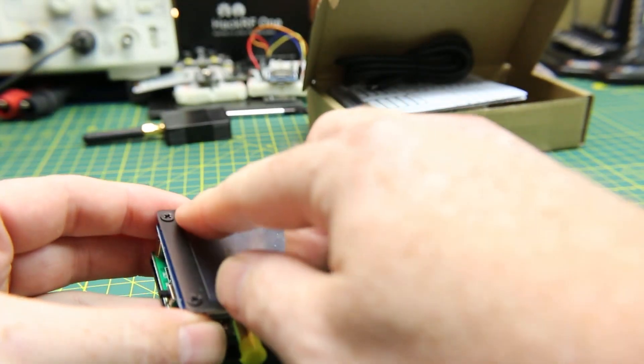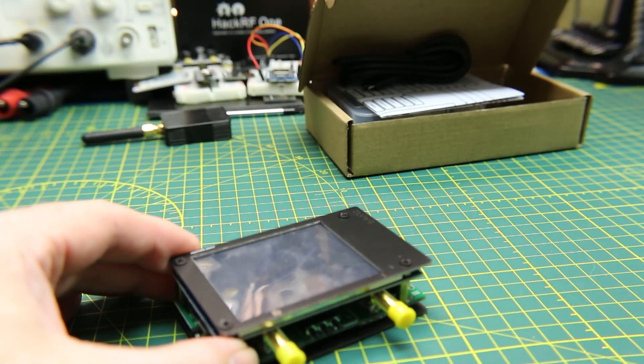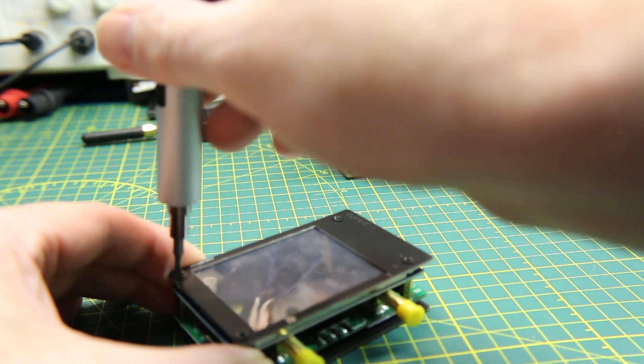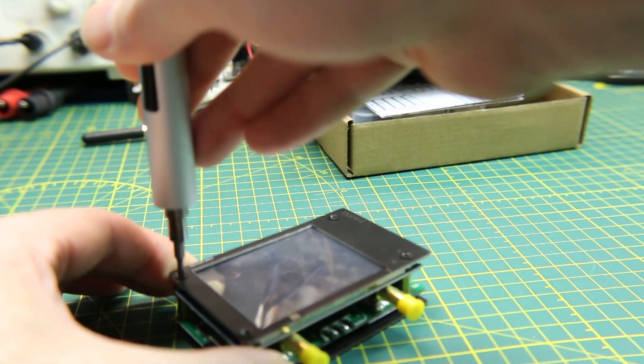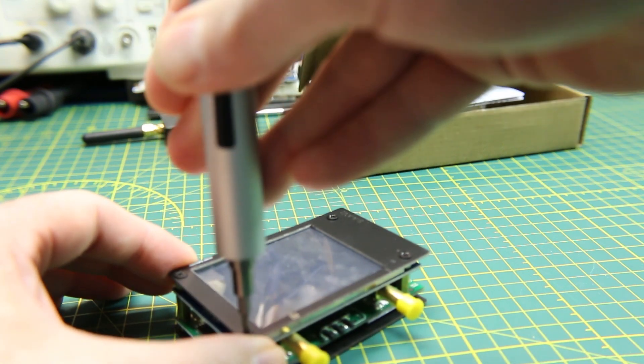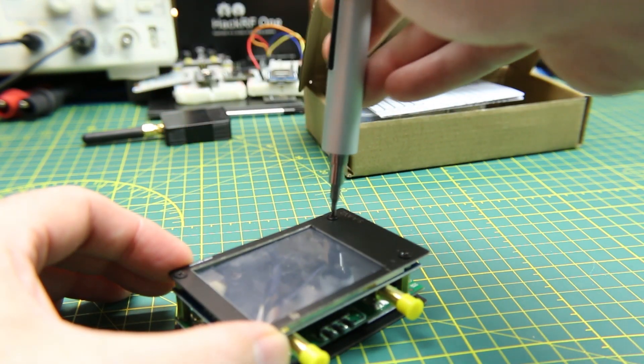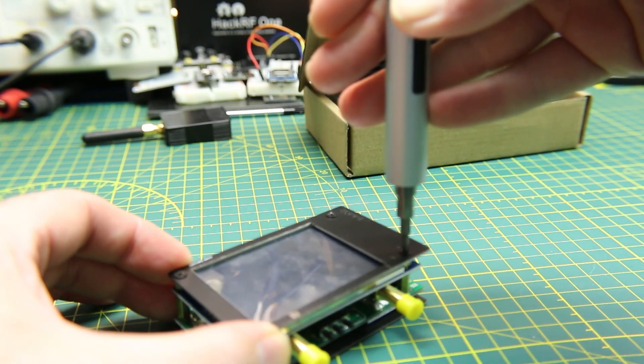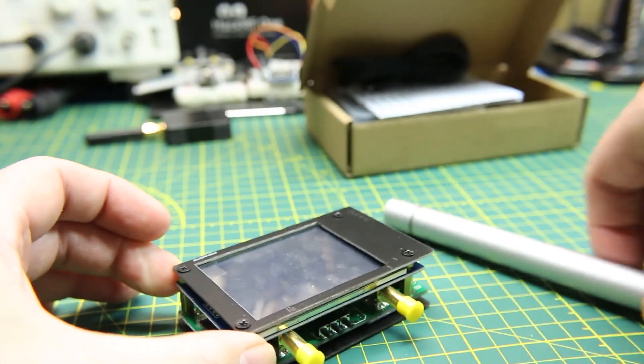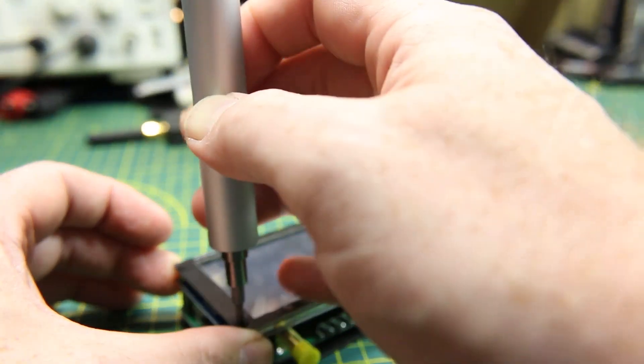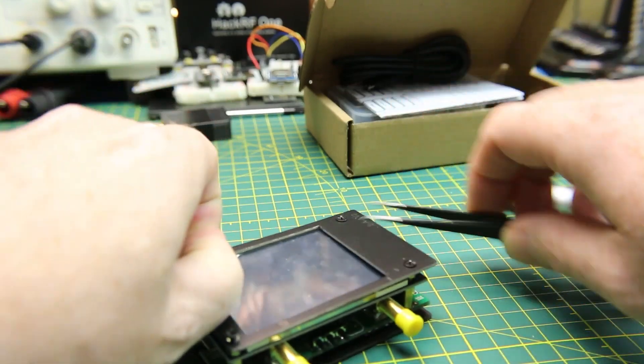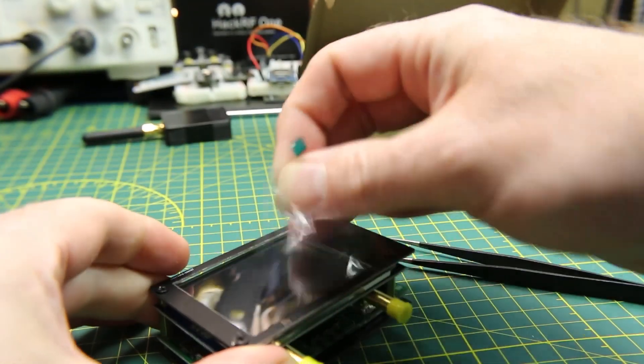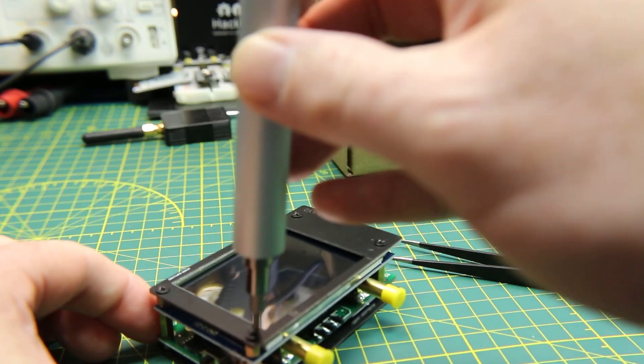Super important note here is that there's a protective film on the LCD that's left on during assembly. You want to disassemble your Nano VNA V2 to remove that film. Don't try to pull it out from underneath the upper layer. Simple Phillips screwdriver. Remove the four screws holding the top face plate on. Then you can remove the protective cover. There's the tab hidden underneath. Once you remove that, go ahead and reinstall your four screws, and we're set to measure some RF circuits.